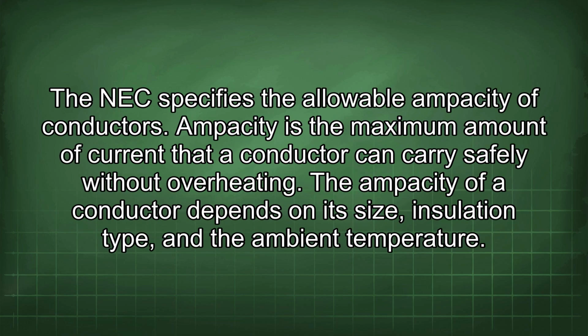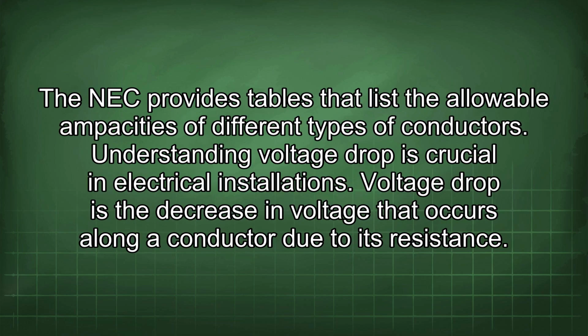The NEC specifies the allowable ampacity of conductors. Ampacity is the maximum amount of current that a conductor can carry safely without overheating. The ampacity of a conductor depends on its size, insulation type, and the ambient temperature. The NEC provides tables that list the allowable ampacities of different types of conductors.